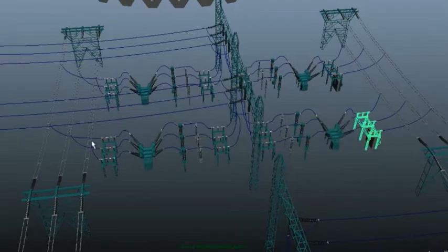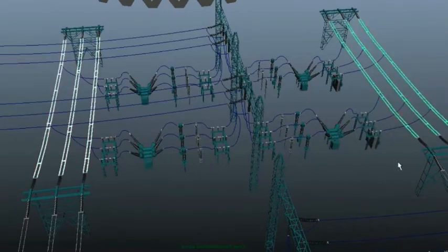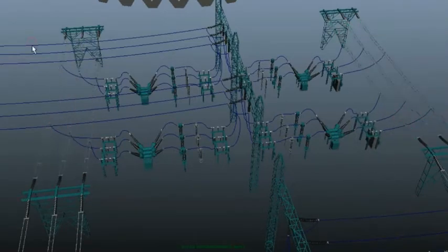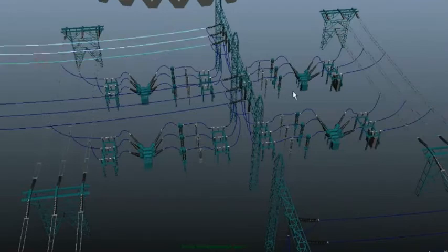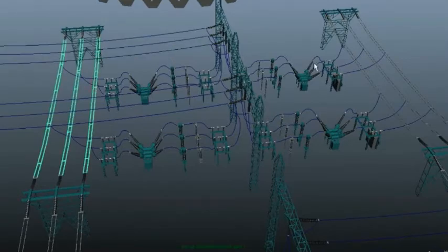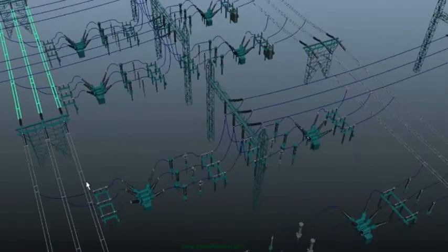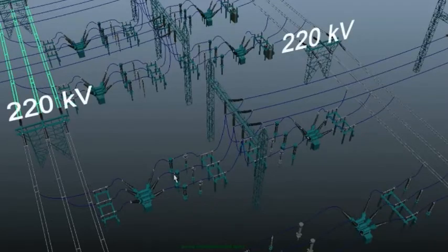As the incoming line is connected to both the buses, if both these breakers are on, the buses remain energized from the incoming power. In exactly the same manner, the connection of the second transformer will also go to both buses. They will go to the first bus from here and the second bus from here. Generally, all the circuit breakers will remain on, so the buses remain energized. Let's consider here that the generation of power is happening at 11 kV and we are stepping it up to 220 kV for further transmission. So, the bus is having 220 kV.